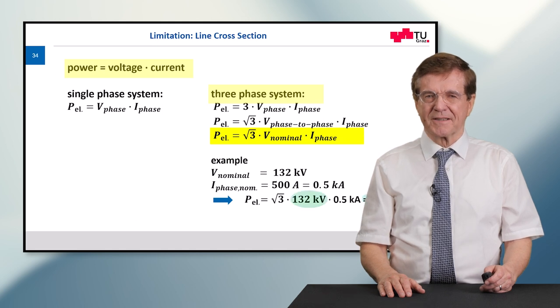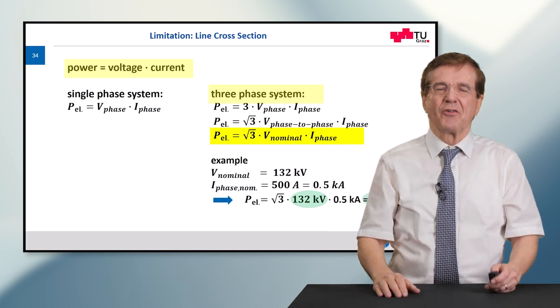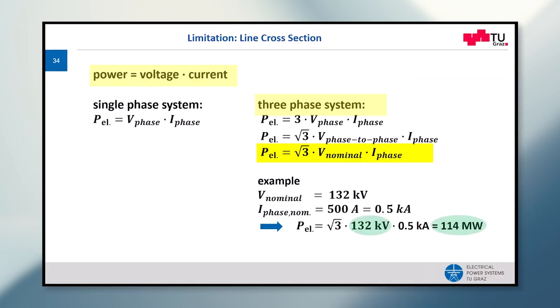Now let's compare two figures. 132 kV results in 114 megawatts. And this leads to a general rule. This means kilovolts is approximately, as a rough estimation, the same as the megawatts. So this is very crude but practical.